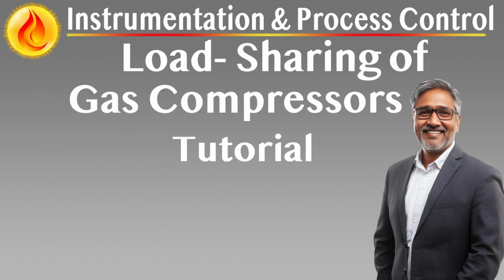By predicting and correcting dangerous excursions beyond pressure or flow limits, the override control dynamically adjusts recycle flow, but always in harmony with surge protection logic. It steps in only when needed, never compromising the fundamental safety of the compressor train.